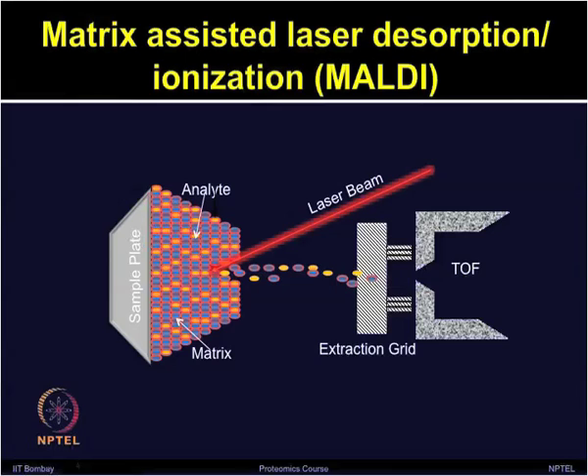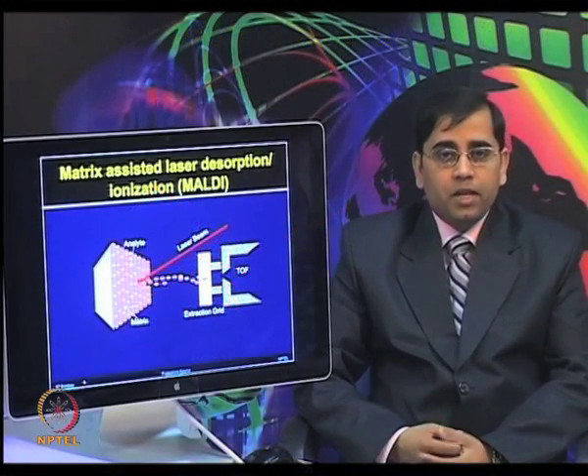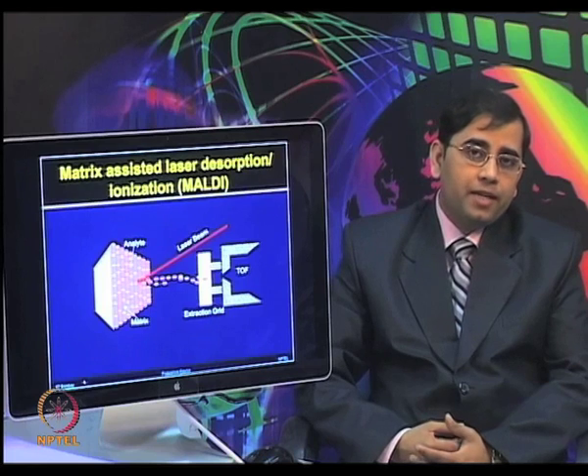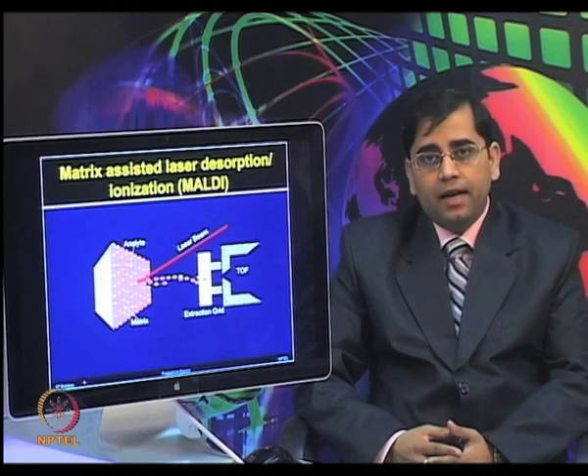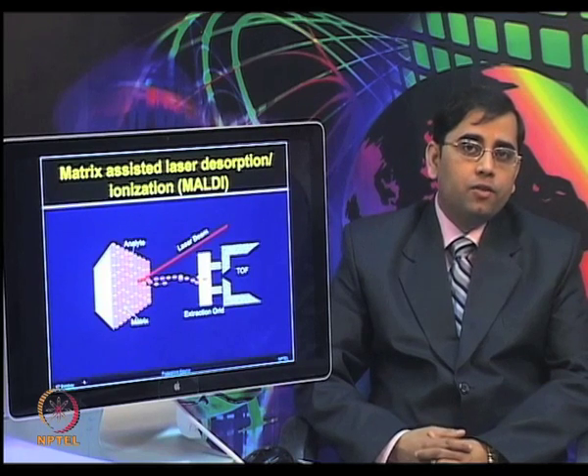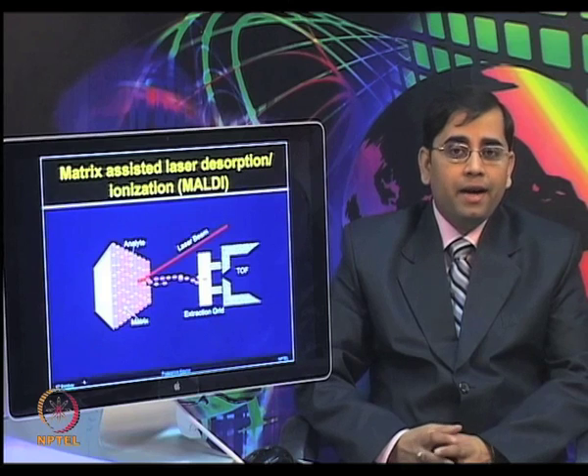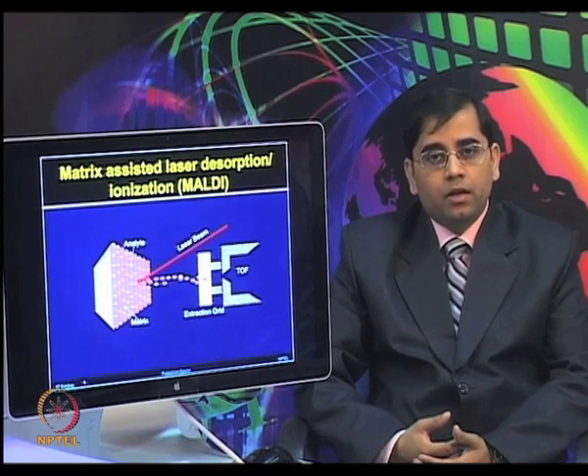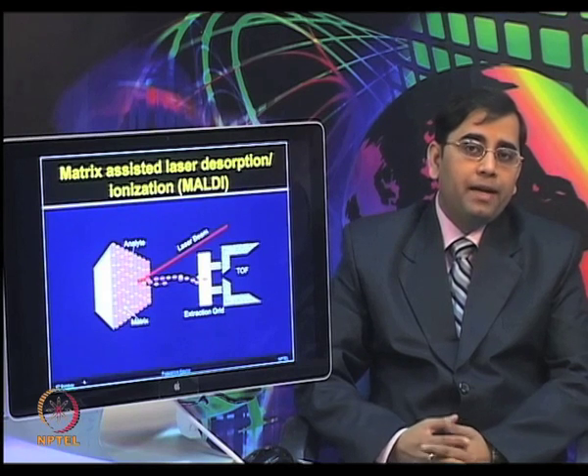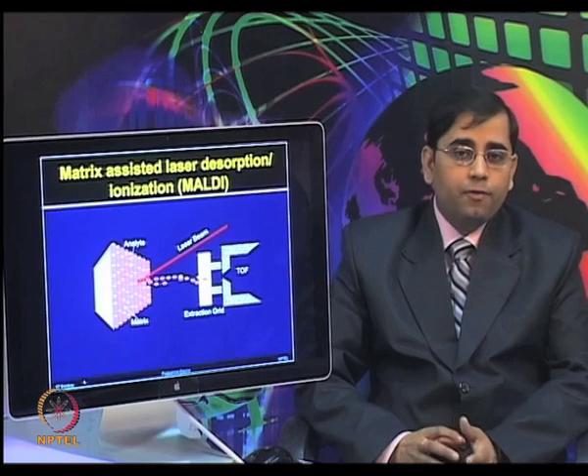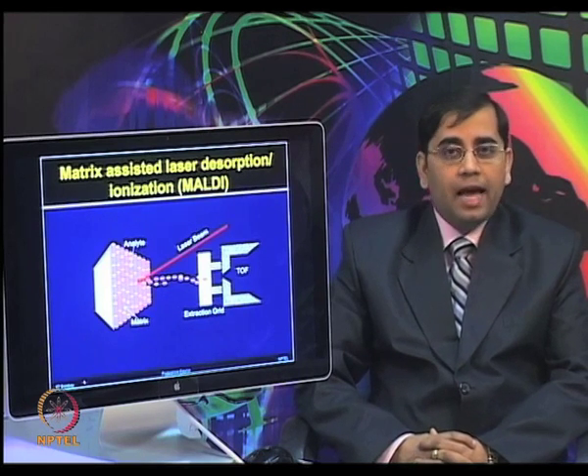In matrix-assisted laser desorption ionization (MALDI), the analyte or proteins of interest are mixed with a matrix, which is usually an aromatic compound. Various types of matrices are available; for example, 2,5-dihydroxybenzoic acid and sinapic acid, among several other choices. Once a matrix is selected, the analyte and matrix are dissolved in an organic solvent and then placed on a metallic target plate. The slide shows how the analyte and matrix are placed together on the sample plate.